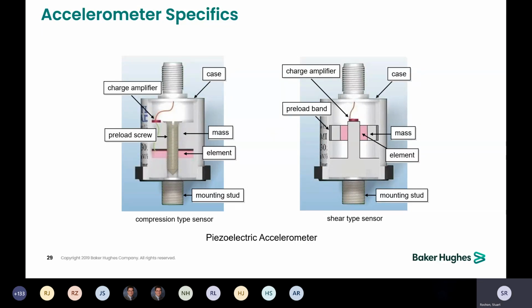You'll see two styles of accelerometer out in the world. The most common is the compression type. It uses a preload bolt to hold an inertia mass against the piezoelectric crystal. The issue you run into is around thermal expansion. All of these components have a different rate of thermal expansion. So under high heat, or where there is a large thermal cycle going from cold to hot, hot to cold, that difference in the thermal expansion of each material can cause what we call stack slip. And as that sensor heats up, you'll see these spikes of 80 or greater Gs, and it has nothing to do with the vibration of the machine. It's just the thermal growth of all of these components.